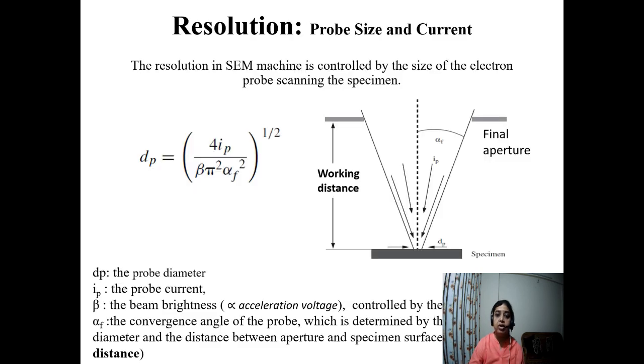Let's move to resolution. Resolution is again a very important parameter for the electron microscope. How can we control the resolution? Because of resolution only, we have shifted from the optical to the electron microscope. In the optical microscope, resolution was decided by the wavelength of visible light. The minimum wavelength possible is 400 nanometers. We can't go beyond that. However, with electrons, because of their dual nature, we can apply the de Broglie wavelength. We can apply an accelerating voltage to accelerate the electron, so the wavelength associated with the electron can be shorter and shorter. So it can resolve shorter features.